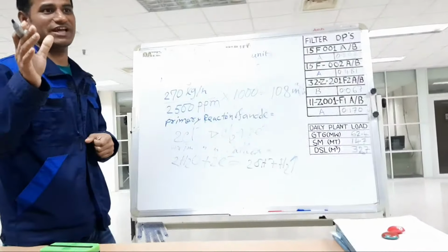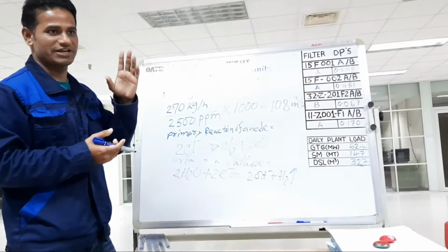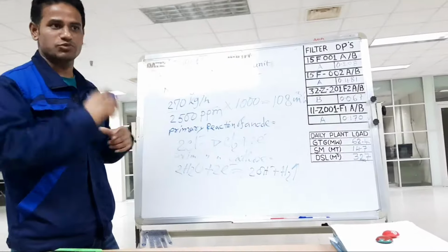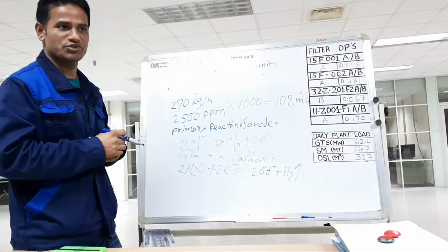But this hydrogen we will vent from the hypodosing storage tank, because this is hydrogen. The hypodosing storage tank has one vent point. From this vent point we will vent the hydrogen, and we will use 2 blowers for this purpose. One blower is continuously running, the other on standby. So this hydrogen is not required.